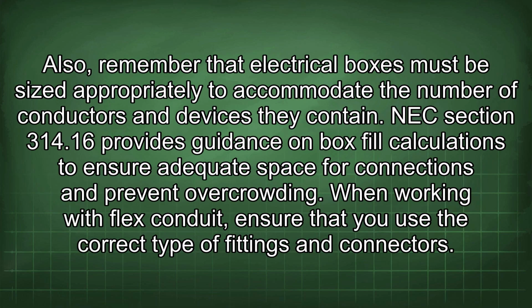Also, remember that electrical boxes must be sized appropriately to accommodate the number of conductors and devices they contain. NEC Section 314.16 provides guidance on box fill calculations to ensure adequate space for connections and prevent overcrowding.